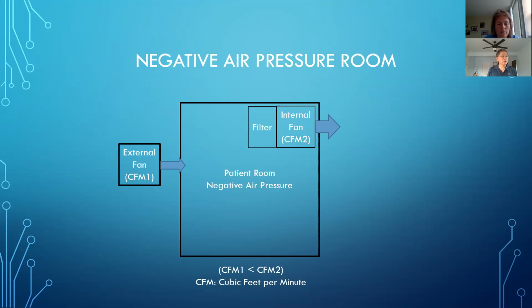Here's the patient room. You have an external air source flowing in at a rate of CFM1, where CFM stands for cubic feet per minute, the parameter for measuring airflow. Within the room, another fan ventilates exhaust at a different rate, CFM2, which is greater than the input CFM rate.